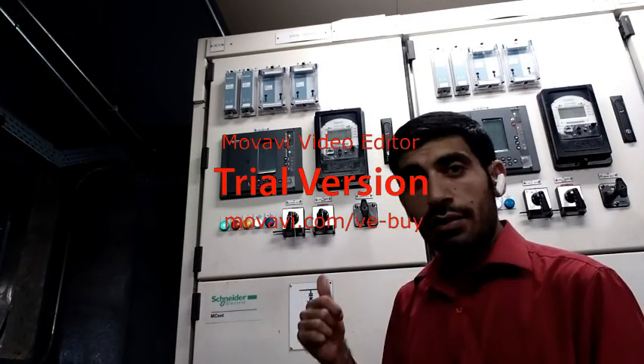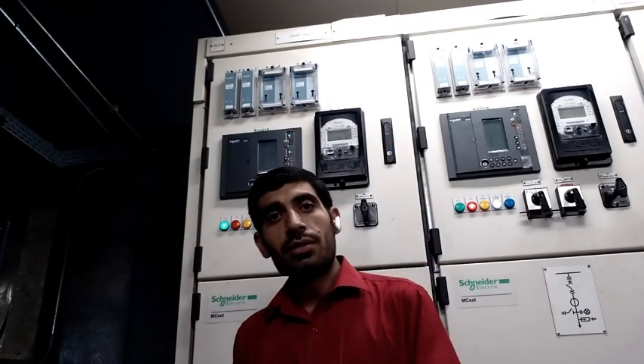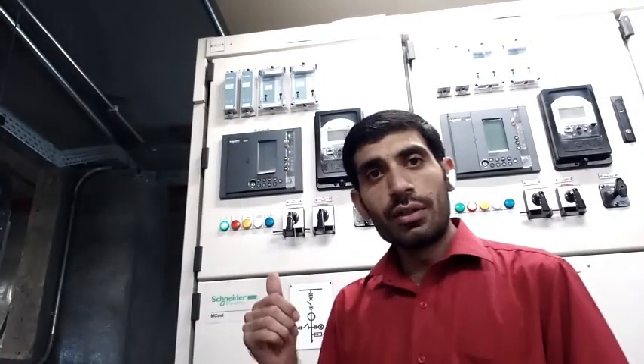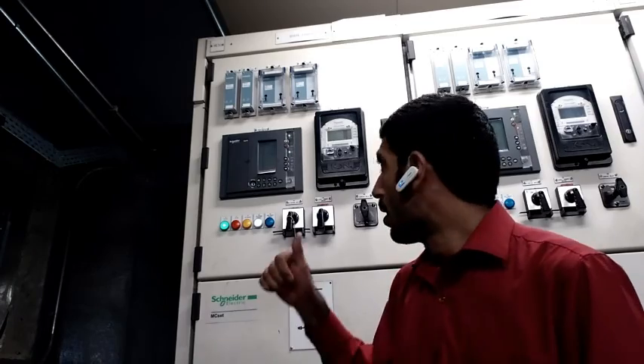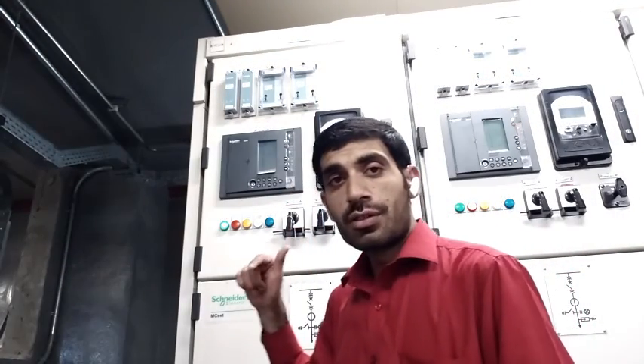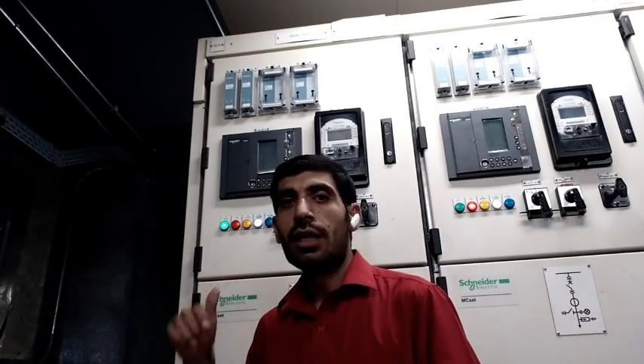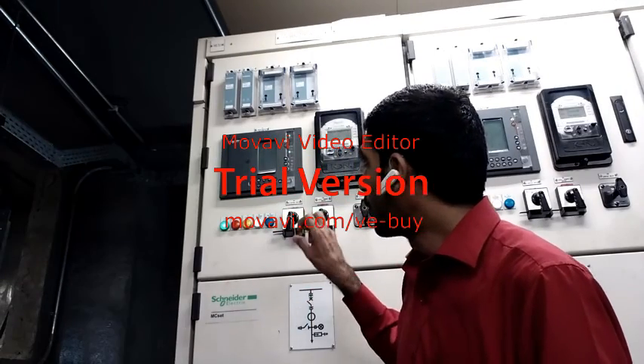And for under voltage, it works the same way: when the voltage decreases by 10% of the rated voltage, this relay will first give an under voltage alarm and will be tripped within the selected timing. So this is under voltage, over voltage, and overcurrent.